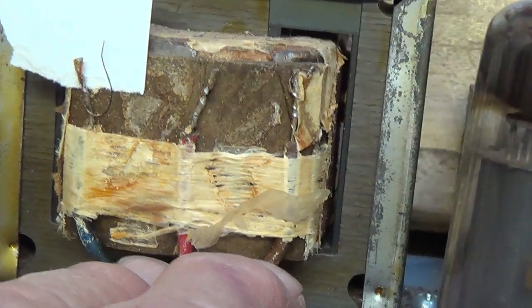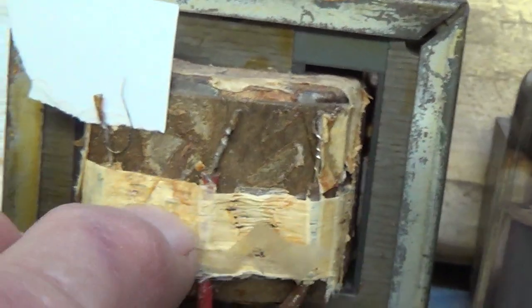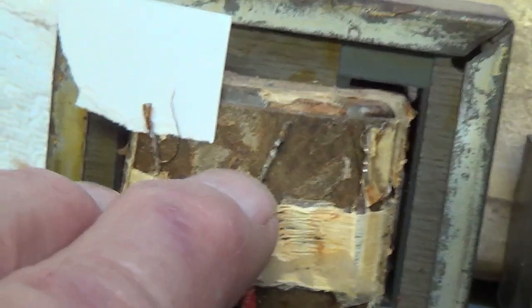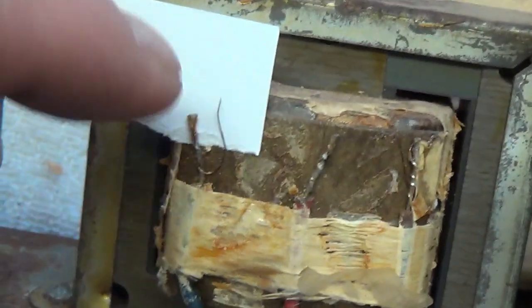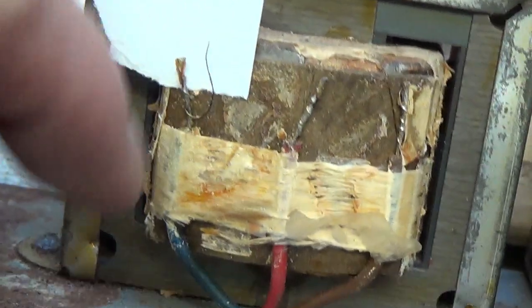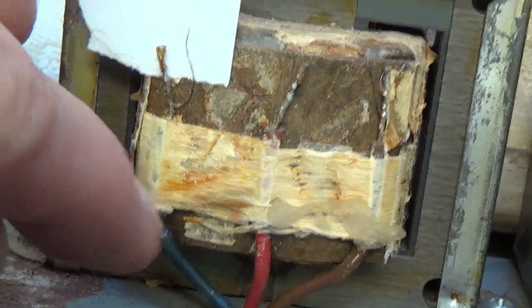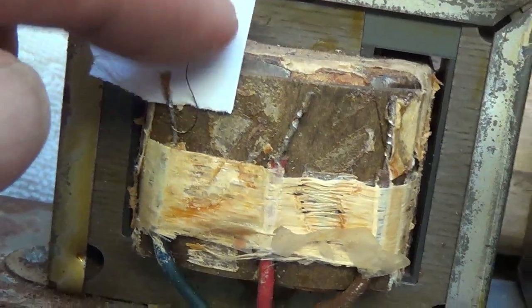You notice that the brown and red wires are connected, and they had that 190 ohms of measurable resistance. But look over here, the connection between the blue primary wire and the winding is broken.